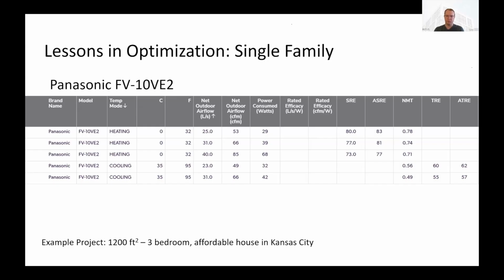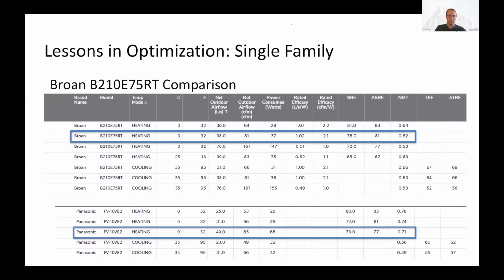And we see it also in the moisture rates. This project originally was designed with one of the Broan units that is much larger, more like a 200 CFM max unit rather than a 100 CFM max unit. And if we were to look at that same, roughly 80, so we're comparing 81 CFM for the Broan versus 85 CFM for the Panasonic, we can see that that Broan has a couple things. One, if we look at power consumption, the Broan is about half the power that the Panasonic is using. So if we're just looking at watts used. The other thing is it's 4% more efficient or 5% more efficient, give or take, at the same flow rate.